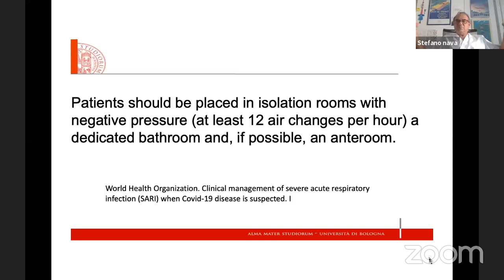So if you go into the WHO document, there is a very interesting statement. If negative pressure rooms are not available, choose rooms with natural ventilation with airflow of at least 160 liters per second per patient. So here, I apologize, this is in Italian, but this is real life. This is our unit. This is not the intensive care. This is a regular ward. And with the help of the engineers, we calculated, according to the wind, how the door should open, how the window should open, how high the ceiling was, how large the room was. They calculated the amount of liters per second. And as you can see from this slide, despite it being in Italian, in each room we could get a satisfactory airflow, at least 2 times more than the suggested 160 liters per second.